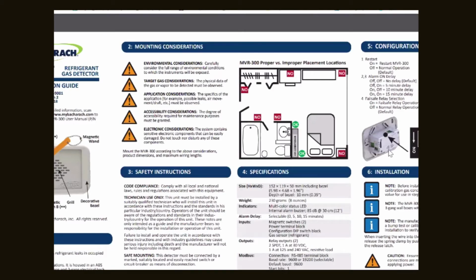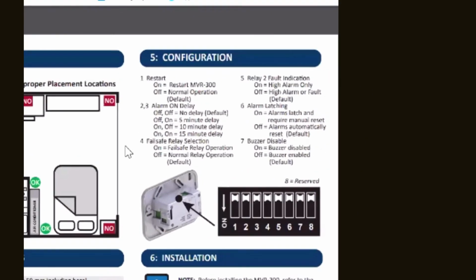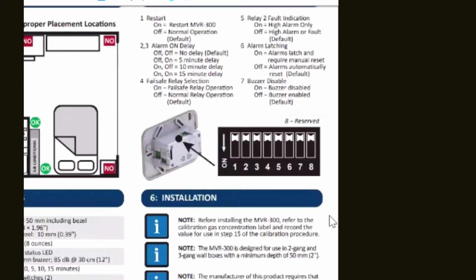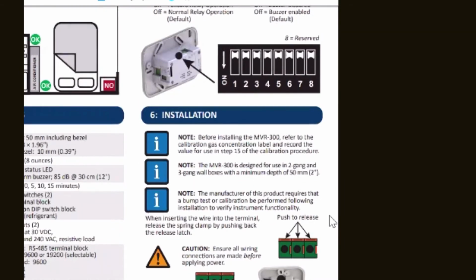Couple other things with the MVR. There are some dip switches on the back for configuration, and it's all about the relay settings, whether they're fail-safe or not, whether there's a delay or not, and whether or not they're latching. So the relays can be configured through the dip switches.